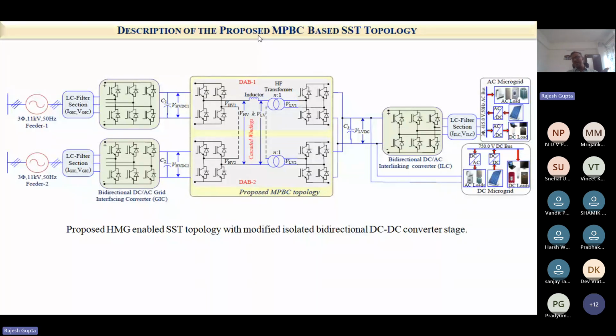If you are well managed within the control range of the converter, it is possible to have a system without a transformer, but then you must have some other way of isolation, like solar power transferring to a battery. So solar is isolated, battery is isolated - the two isolated, I don't need any other isolation. Then it is okay, for a passive load, because normally in active loads, two-side transformer is preferable.